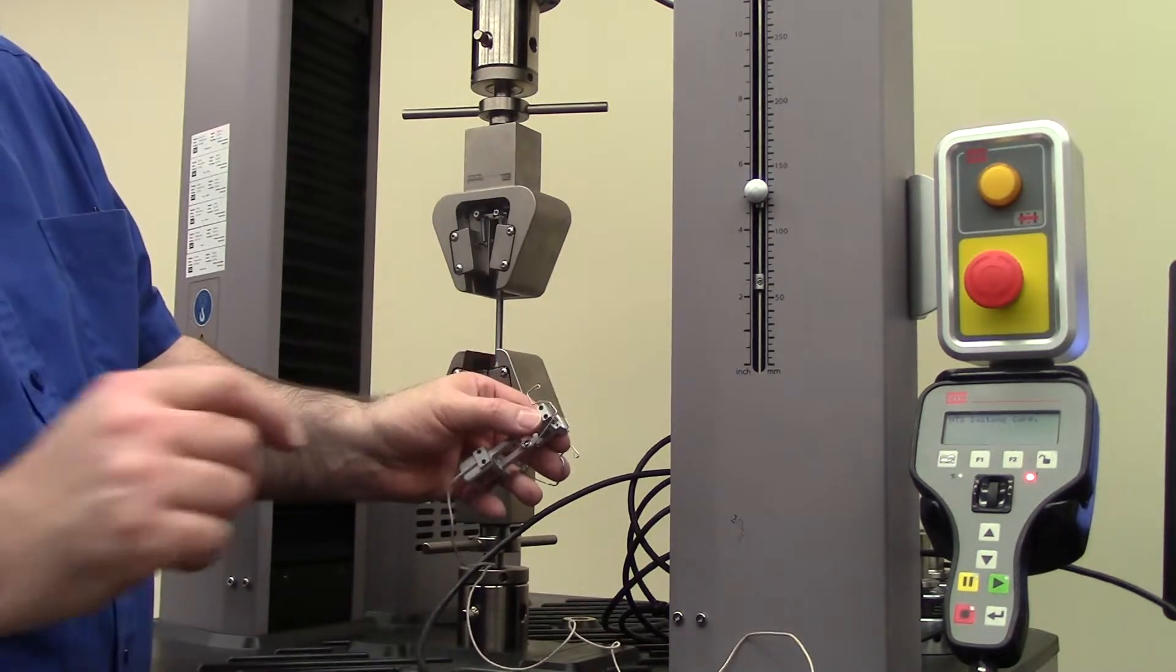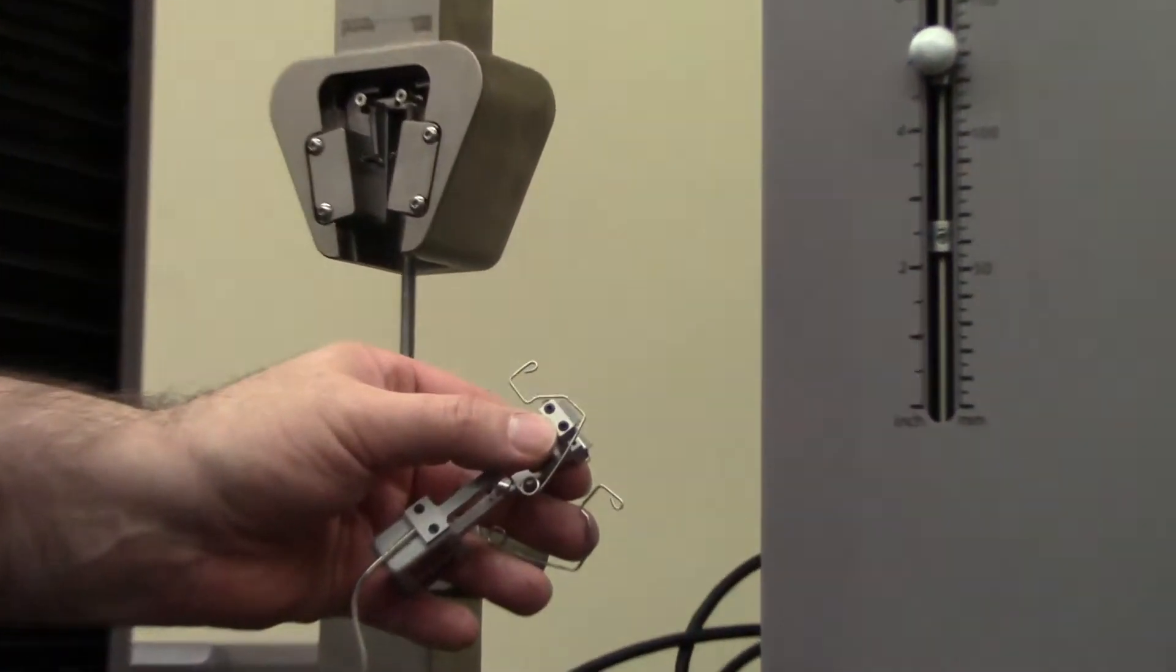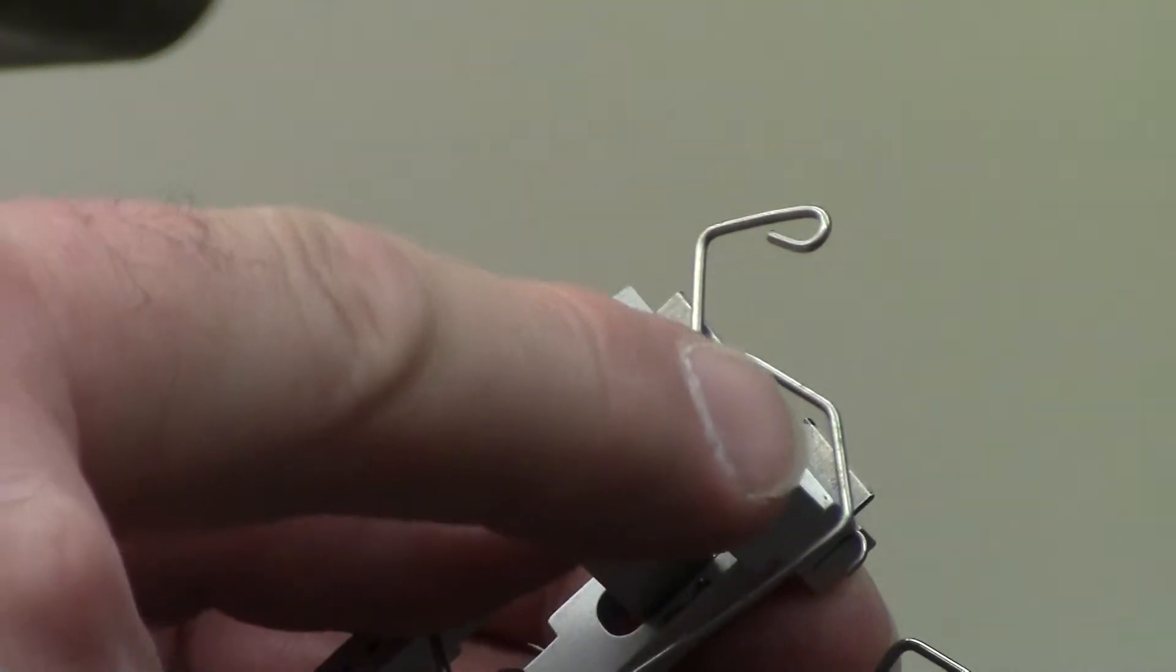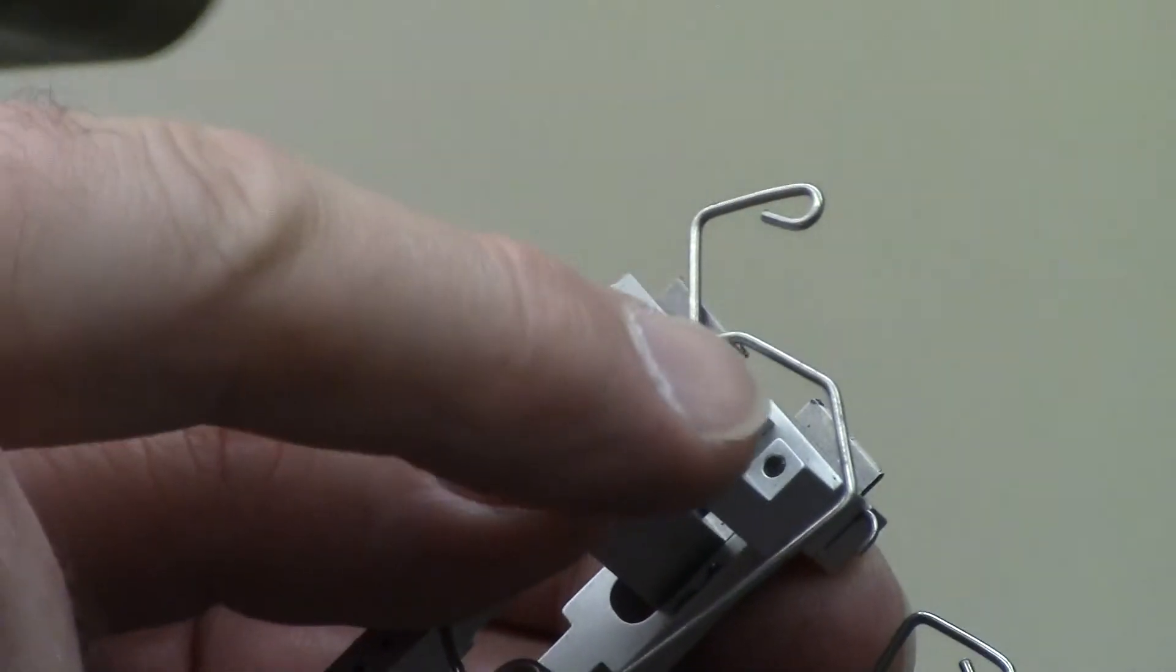There's indentations on this. Let me see if I can zoom in on it a little bit. Okay, we want this middle point to be on the other side of the specimen from the blades. I've seen people hook it up wrong, and I'll show you what that looks like. We want this middle point, not this one over here and not that one over there, but the middle point just lined up with the specimen.